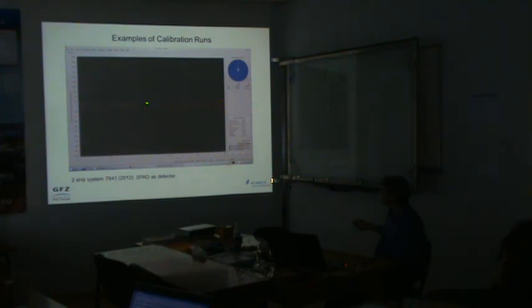And here is an example of a calibration run recently, when we had switched over from 10 Hz to 2 kHz and were using a single photon avalanche detector. This is what we call a SPAD. Now you see the line in the center is much more populated, because we usually perform about 10K returns. It takes only a few minutes. The average return rate is in the order of 5%. It's not very well readable, sorry for that. The mean is about 78.5 nanoseconds, and the standard deviation per shot is in the order of 15 picoseconds only, because we have a very short pulse laser and a high-speed photodetector.